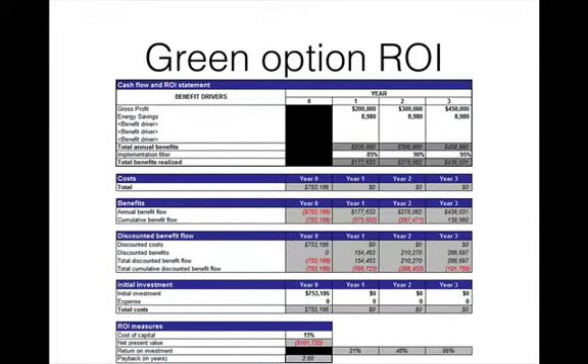With the redundant system and green options of solar grids, the total cost becomes about $750,000 and increases the cost by almost 30%. When calculating the ROI, there is also consideration of benefit of cost of energy savings of about 20% or about $9,000 annually. We can see that green option ROI will be smaller, but the difference is not big enough to justify not using it. The overall payback occurs in 2.68 years. We also gain the benefit of perpetual energy savings.